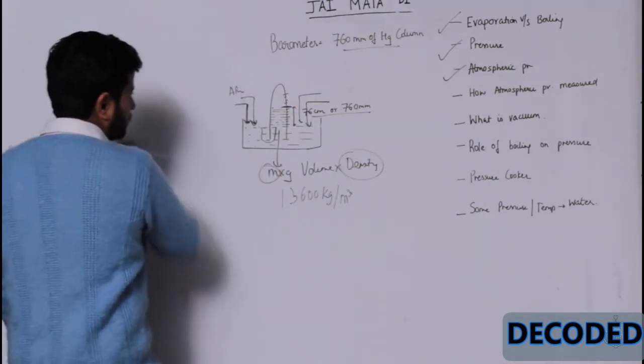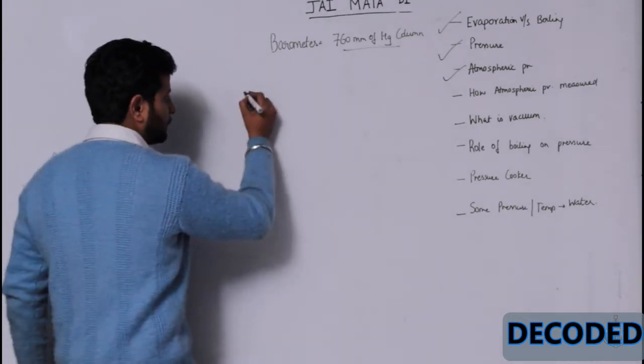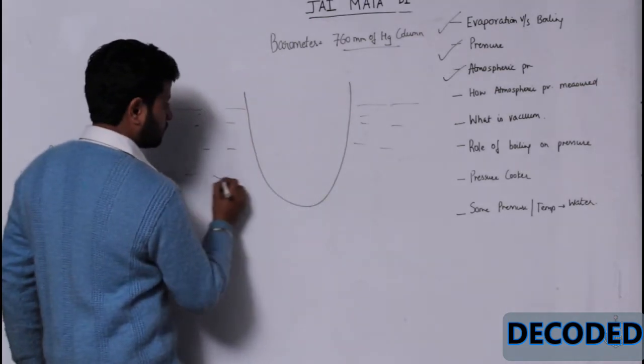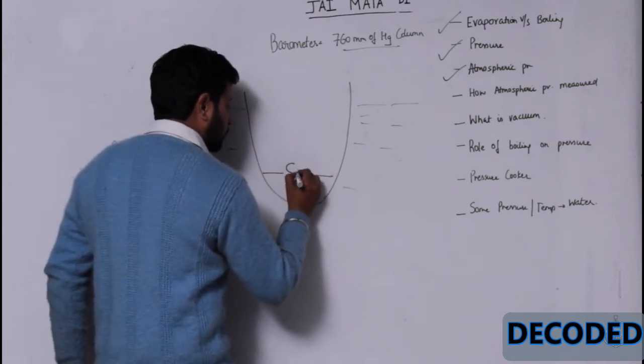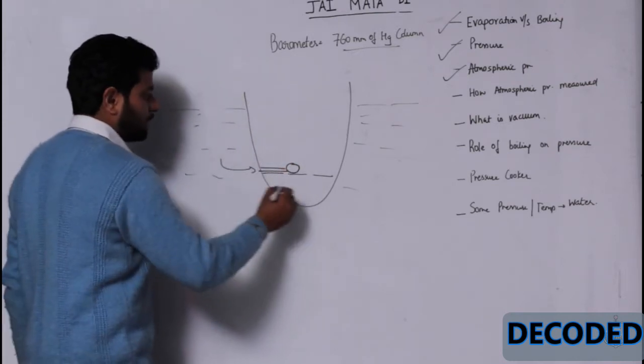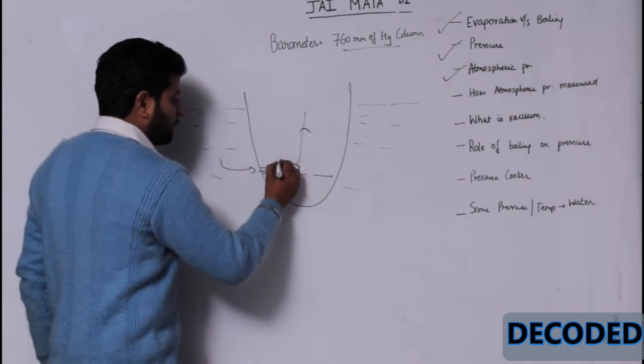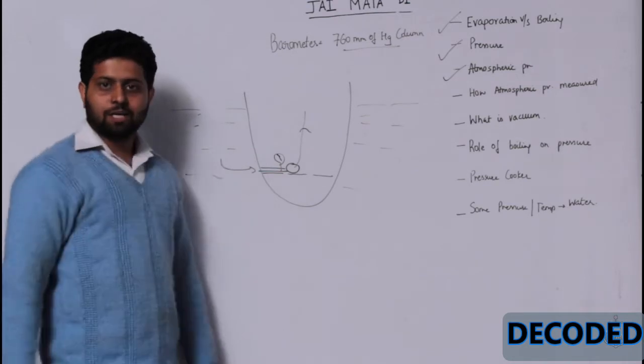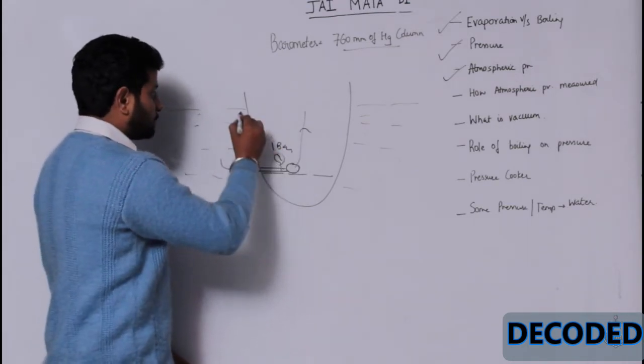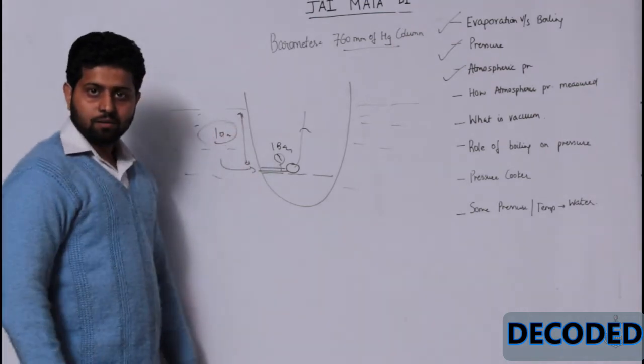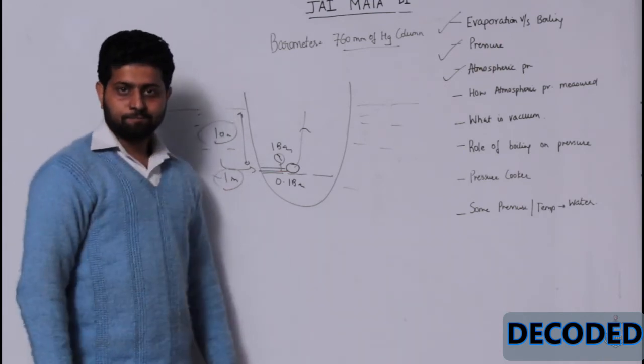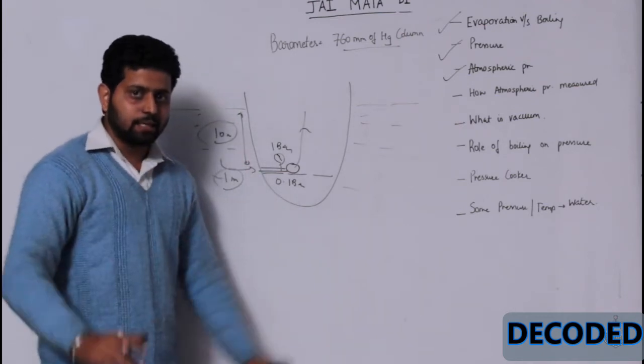When we are on a ship, the ship is like this, and this is the water level over here. A pump is situated over here which has got a pipe like this. It is taking suction here and then giving wherever you want. There is a pressure gauge fitted over here on ship. Just by looking at the pressure over here, we know how much underwater we are. If it is 1 bar, that means we are 10 meters below the water level. If it is 0.1 bar, that means just 1 meter below the water level. These calculations are important when we talk about NPSH.